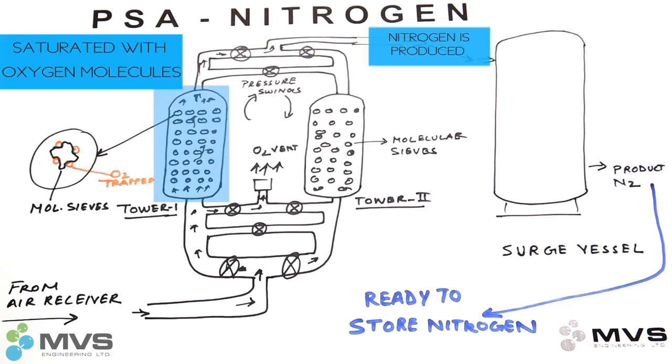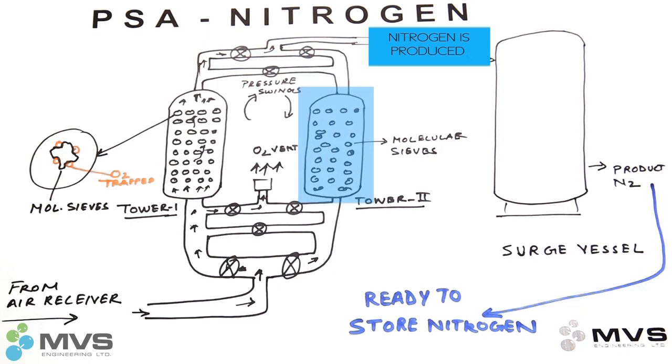Then we switch over to tower 2, which then gets pressurized by compressed air and starts the production of nitrogen. In the meantime, tower 1 is depressurized and the oxygen molecules are released back into the atmosphere through a vent port.